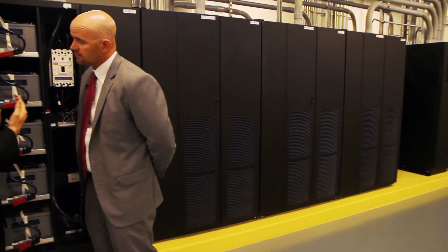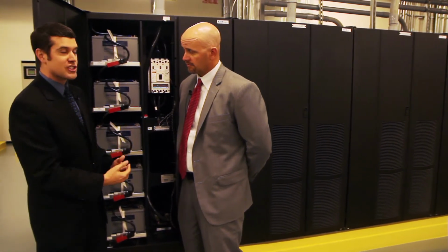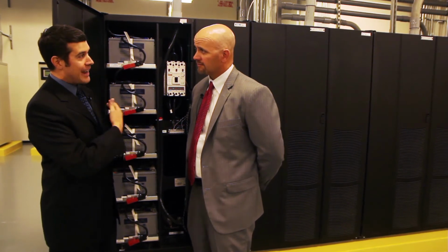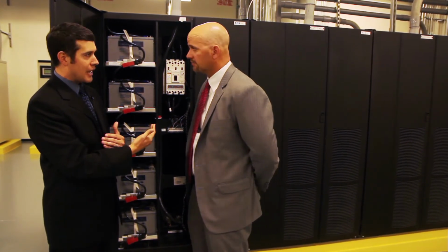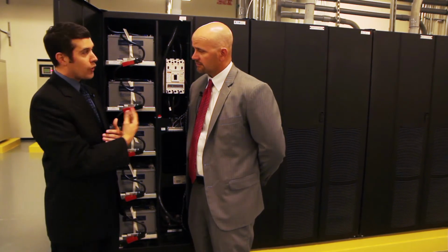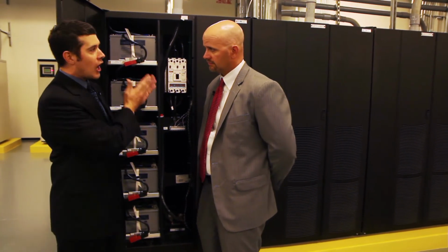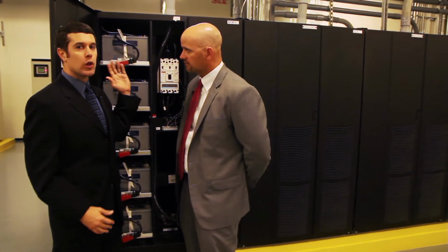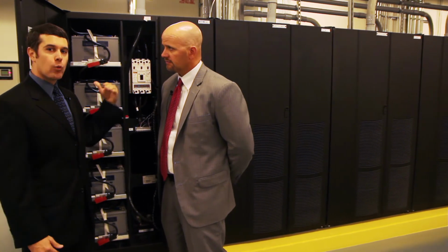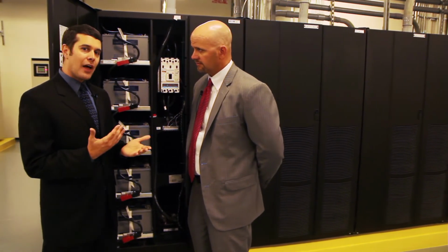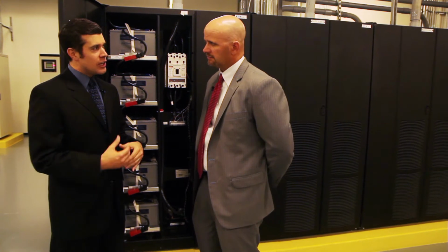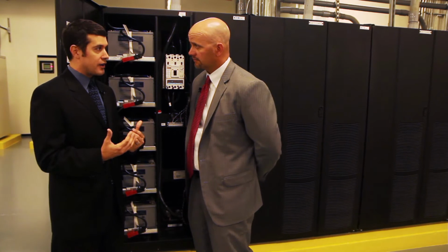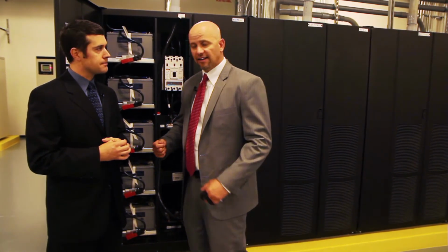And so as you look at the amount of battery power or the amount of time that it can sustain the equipment, that's one thing. But if you wanted to maintain this rack of UPSs, or basically the controller for these batteries, you have to have a whole another one, being the N+1. So on the back side of this, you will have one whole additional row of batteries and one additional brain as well. We talked before about how it's very difficult to have redundancy in everything, but this is not where you want to not have redundancy.